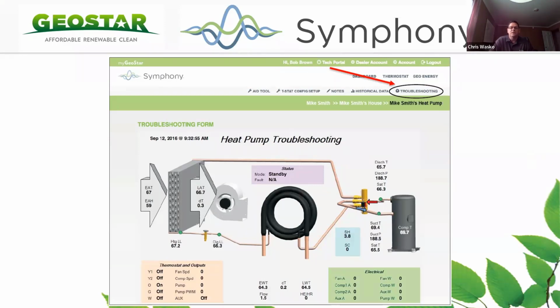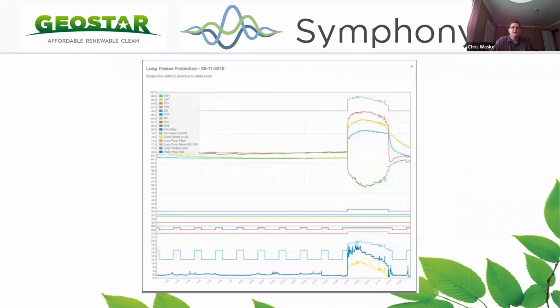So this goes a lot further than just being able to look at data and information. It's going to play a big part in your technical abilities to service your consumers remotely without having to go to their home, and to be better prepared for that service call or for what you may find when you get there. It gives you large chart systems. It's going to allow you to see the compressors, what stage they're in, or if it's variable speed, where they're staged at in their speeds, and what time that change happened. And you'll be able to look at these data points based on possible failures.